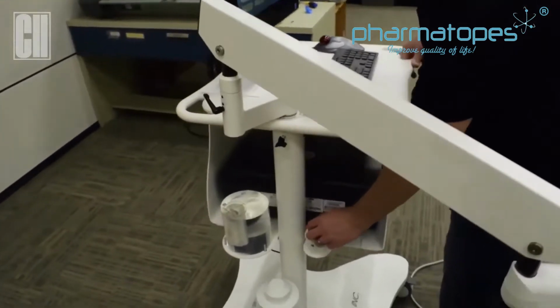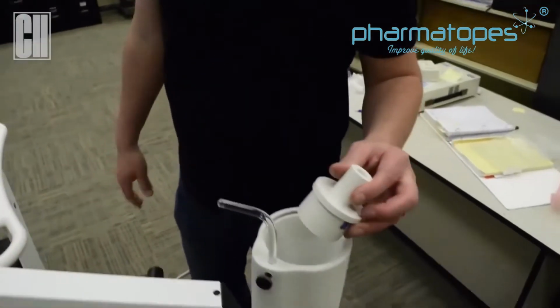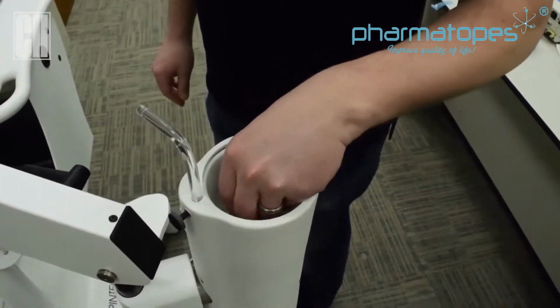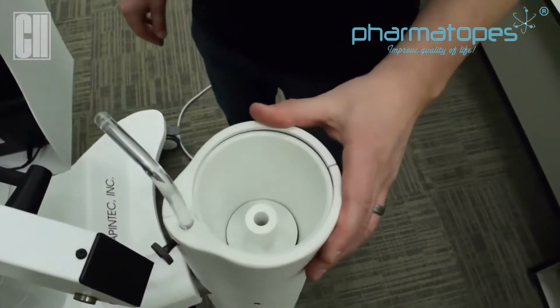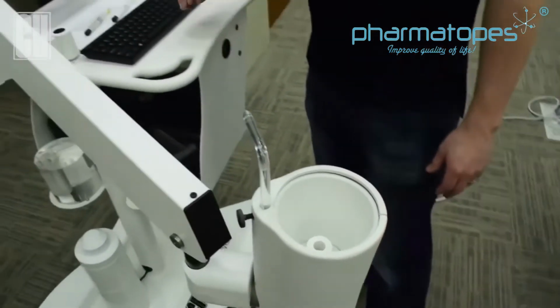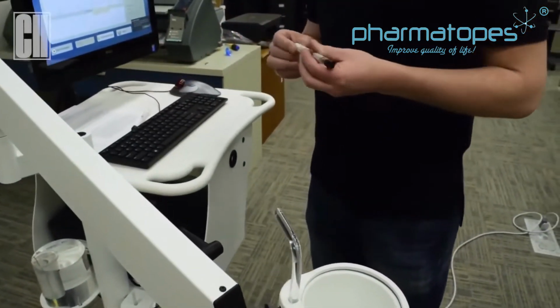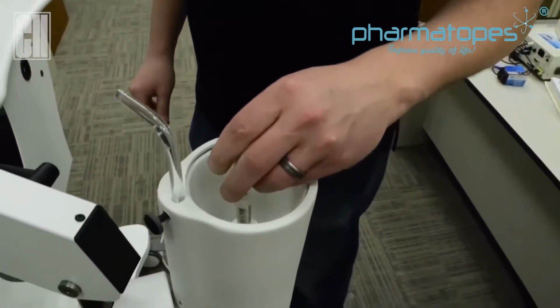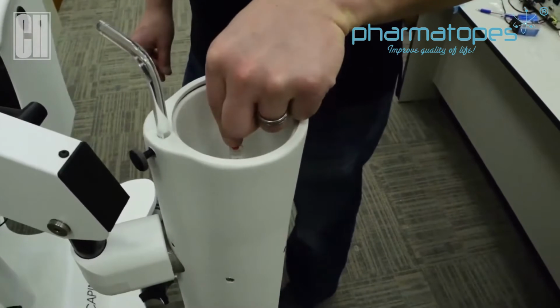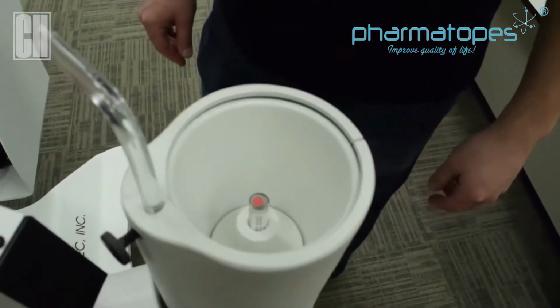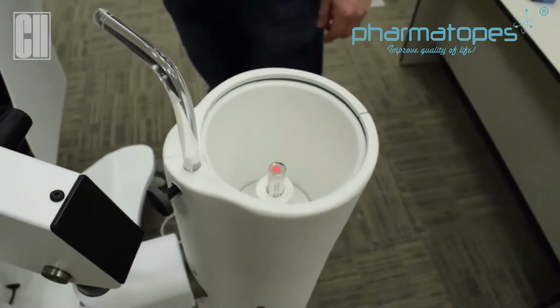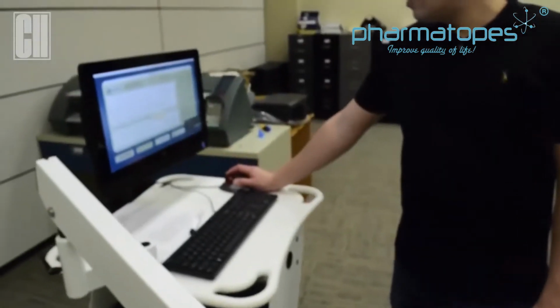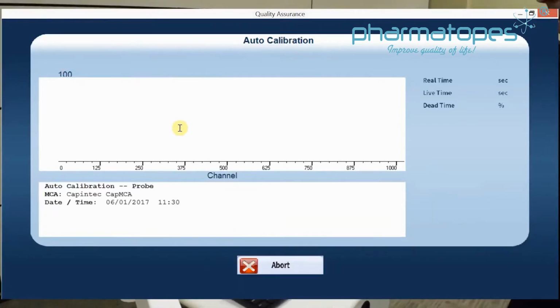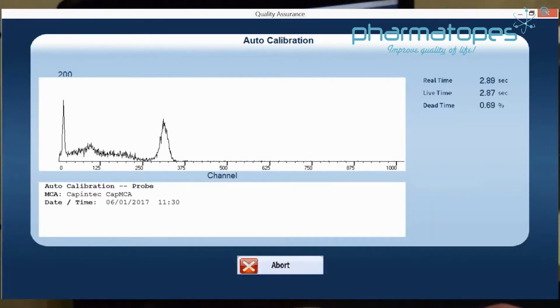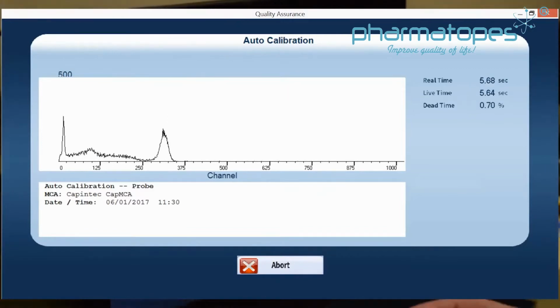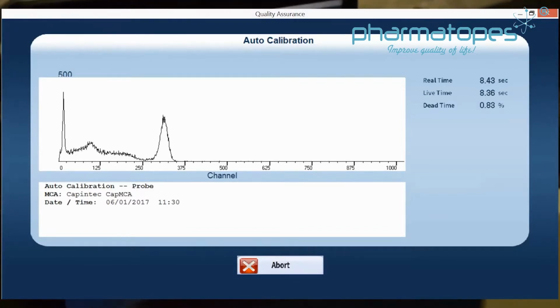So for the probe, you want to get your source holder, place it down into the probe. There's a lip which catches this, prevents it from hitting the detector, causing any damage to the detector. Once you have that lined up, you'll grab your cesium source with your black tip down, position it into the center, and you want to make sure that that tip, you could feel it touching the detector down into the probe. Once that's in position, you can click OK to calibrate, and you will see your spectrums, and it will make adjustments to the spectrum until it's successfully calibrated.